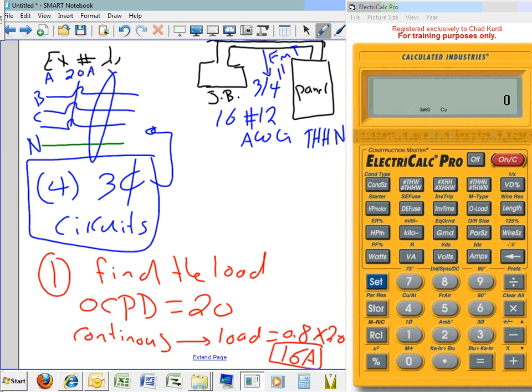Piece of cake, right? Assuming that each one of them is 1 amp. If it's not 1 amp, you do your math. Take the volt amp divided by the voltage, get you the amps, and add the amps. You shouldn't add up to more than 16 amps on every one of the single pole 3-phase circuits. Any question, guys, about this up to this point? Thank you. We're not done yet. So that's find the load based on continuous load. My load, based on continuous load calculation, should not be more than 16 amps. Everybody agree on that one, at least?